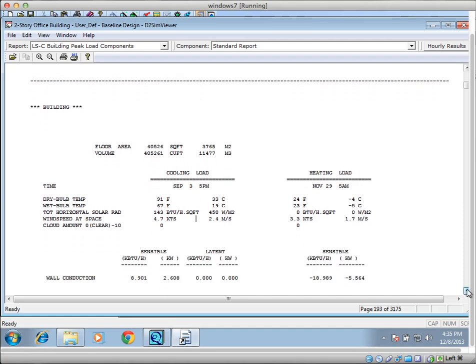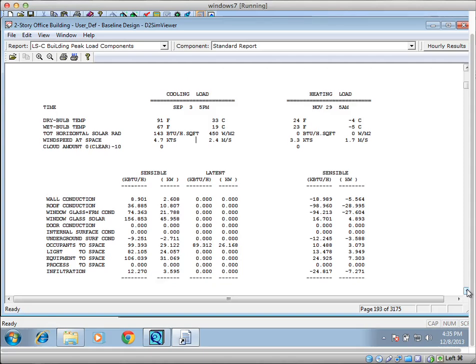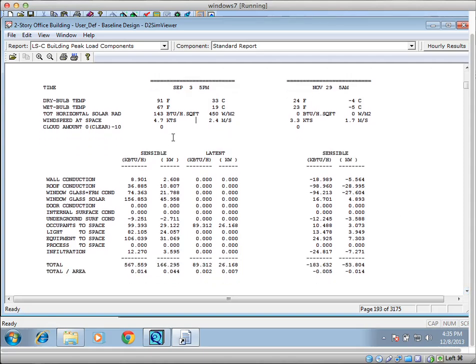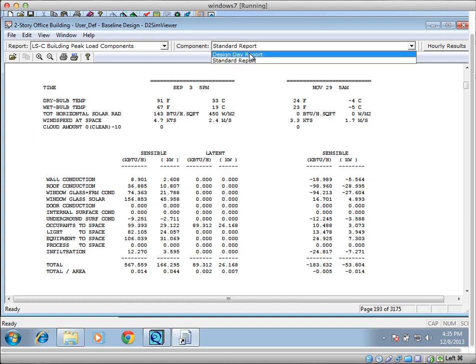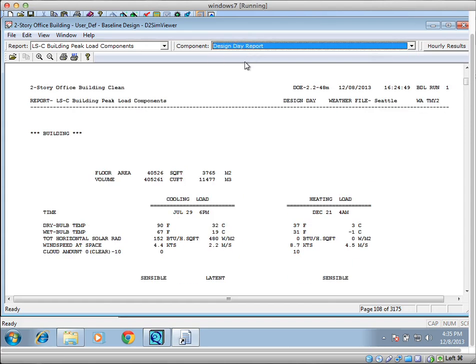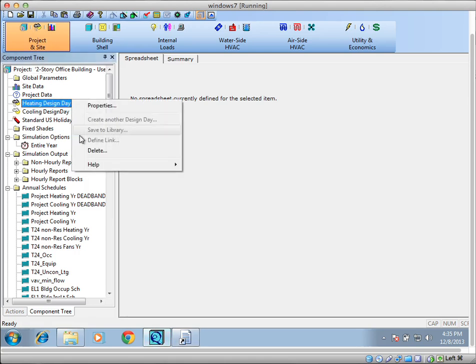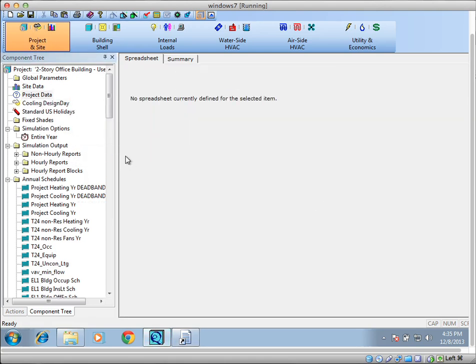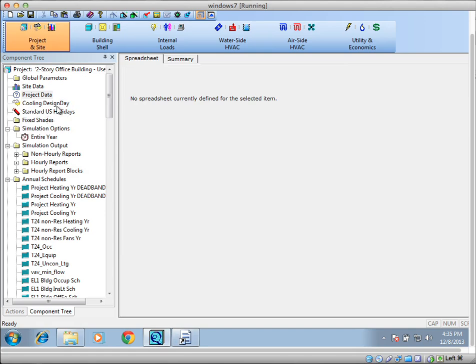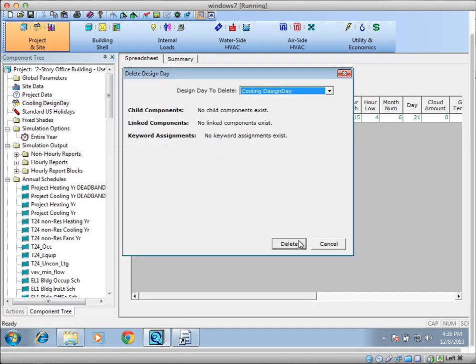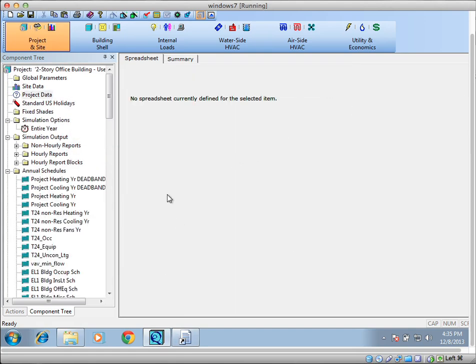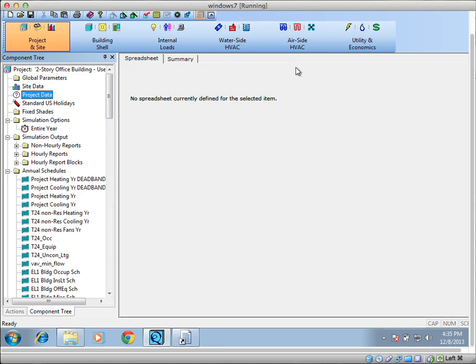Sometimes, so that is actually hotter. So what might be happening in this scenario, if we were to look further, is the HVAC system might be slightly undersized, and we might have slightly more hours out of throttling range than not. Sometimes if I do have too many hours out of throttling range, and I've neglected to look at my design day conditions, a lot of times I will go over here and delete these, and then run my model without any specified design days. The reason I do that, ideally, is to see if the model will size itself using just the weather file and result in less throttling hours. Sort of a way of checking like, is this the problem? Is my design day the thing driving me crazy and making the model not converge? Just an option.